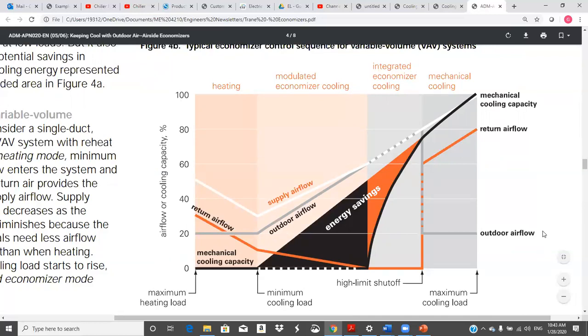The ventilation air is going up to handle that. And so the return air is ramping down at some rate. And so this plus this equals the supply air. Okay, and so as it gets hotter and hotter, we're still not doing mechanical cooling. It's getting warmer. We need more ventilation air. It's going up. This is ramping down. And the total supply airflow is going up because we have more cooling load in the space. And then we get to the point we can't cool it with the ventilation air. So now the mechanical cooling starts, comes up here. We're still on all ventilation air. We hit the high limit shutoff again. Bingo, this comes down here. Then the return air jumps up and we continue on. So it's a pretty similar story, but the picture looks a little bit different.